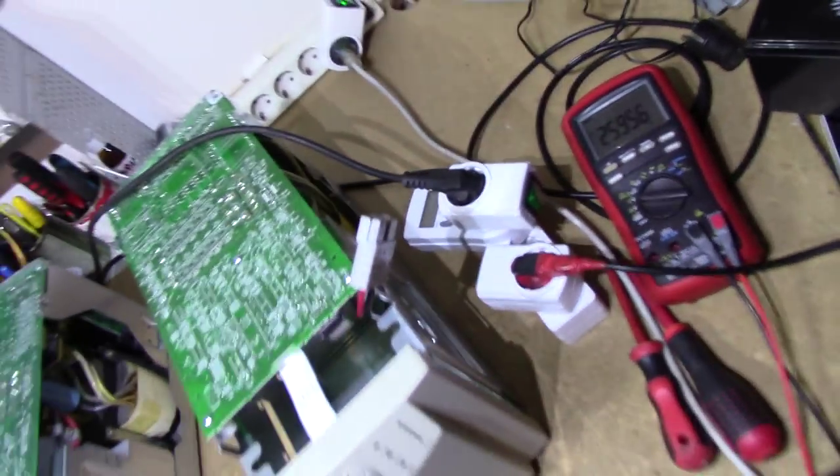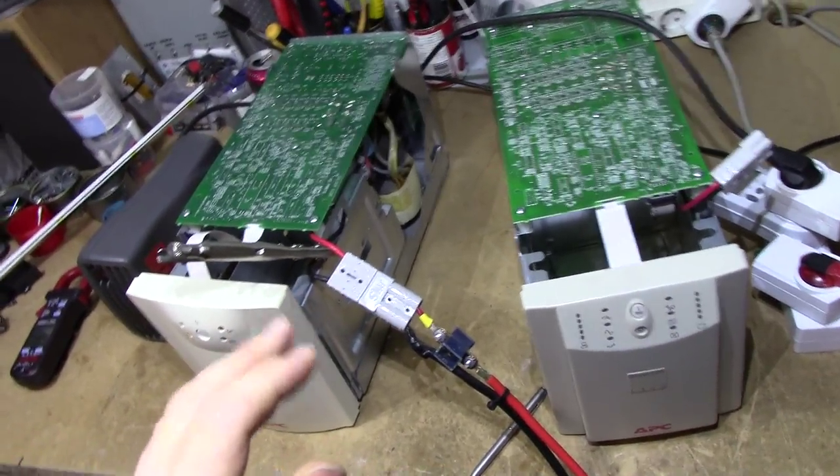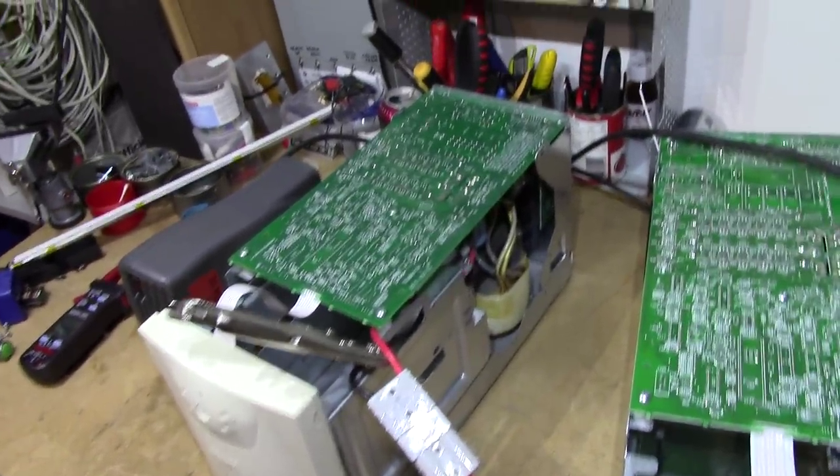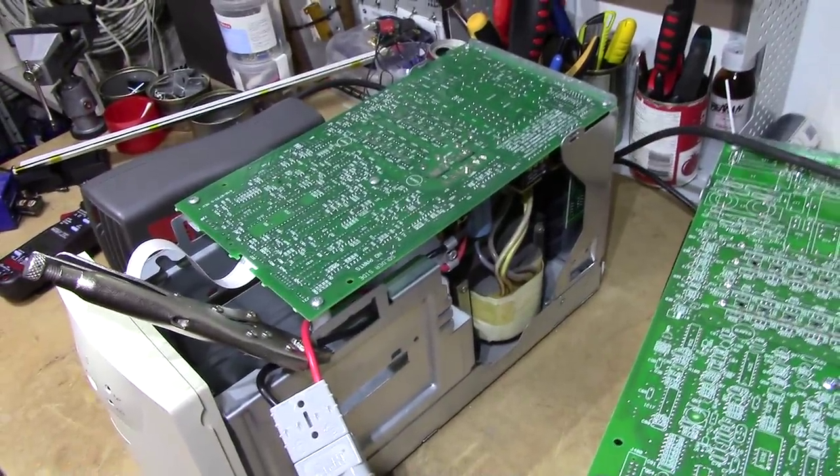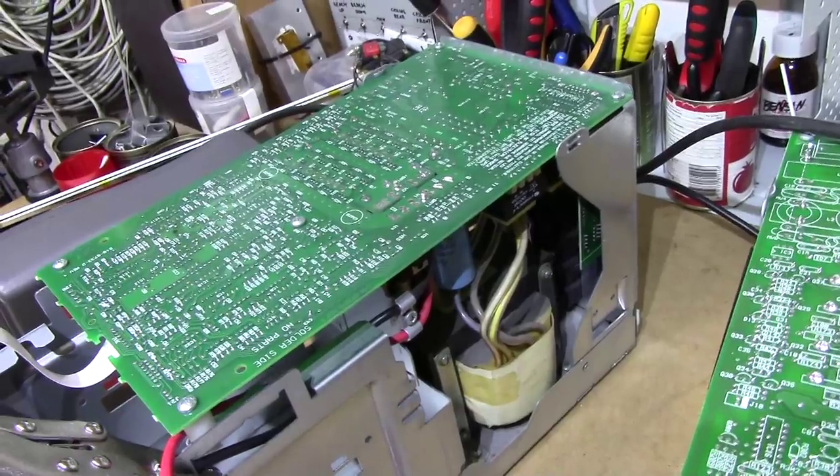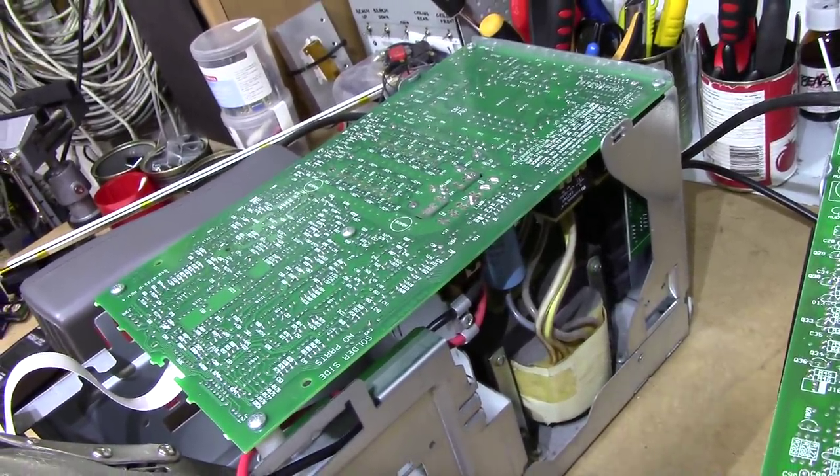What I believe has happened with this unit is that it suffered a failed mains output filter somewhere in the inverter, because high frequency noise is coming through the transformer where it shouldn't. So it's probably got a bad cap, either on the output or on the input of the transformer.